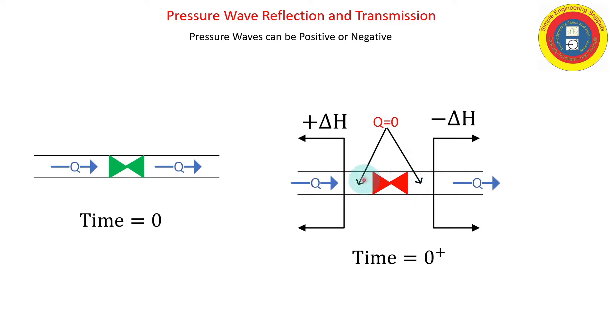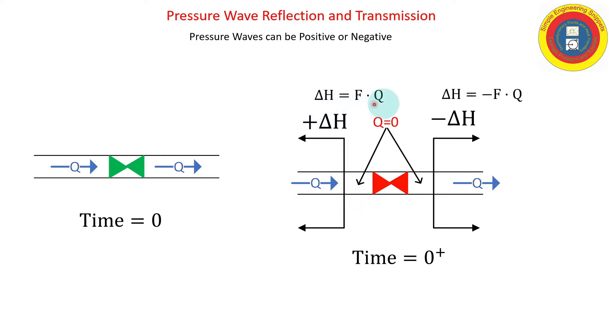Slamming the valve shut brings the flow to zero on each side — ignoring cavitation and vapor formation downstream. There is a negative pressure wave propagating to the right, bringing the flow to zero on the downstream side. On the upstream side, there is a positive pressure wave propagating to the left bringing the flow to zero. Both of these can be calculated with the Joukowski relation.